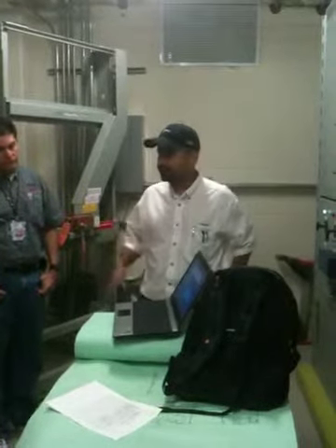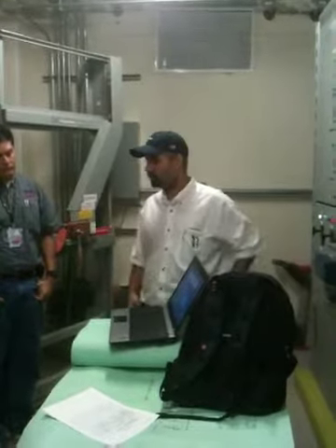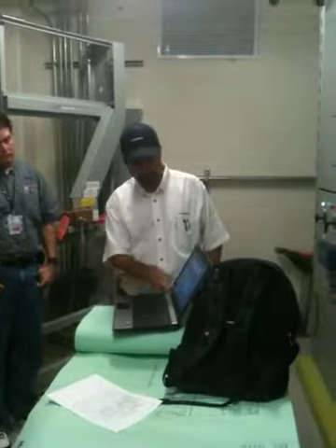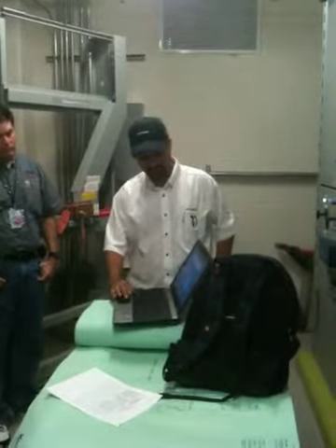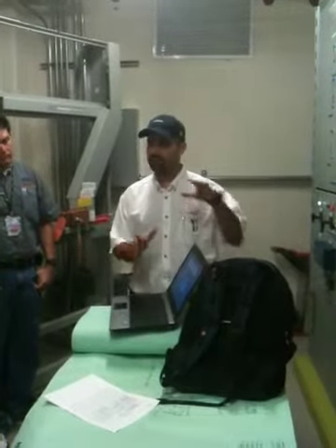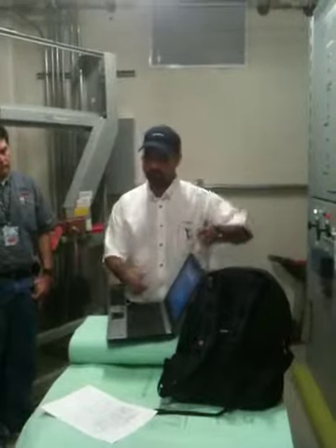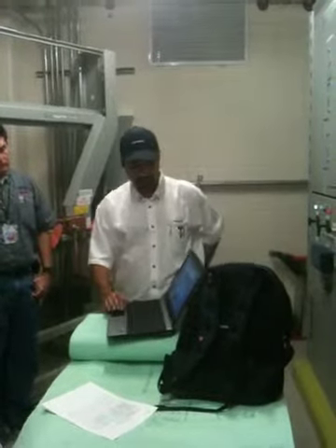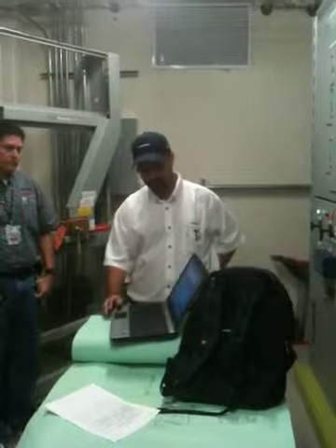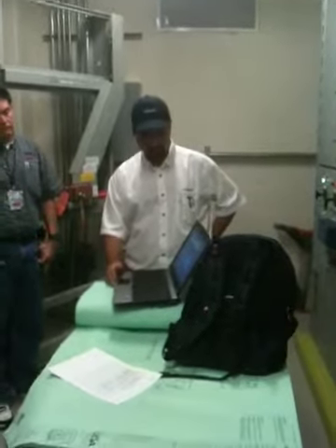Now, on a fire alarm, first, of course, you go investigate. If there's no problem, you go ahead and silence. Right now we have the alarm, so acknowledge alarm. Acknowledge will acknowledge it at the panel, but the alarm will still be blaring and going off. To silence that, you have the option to do silence audibles.